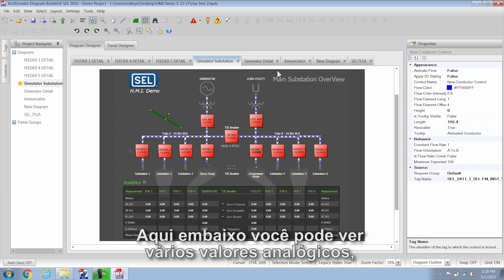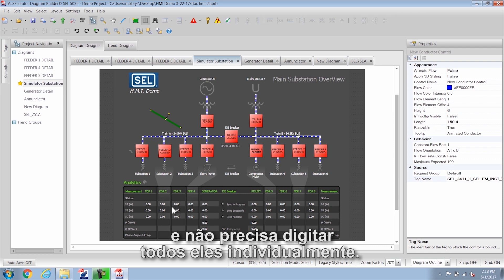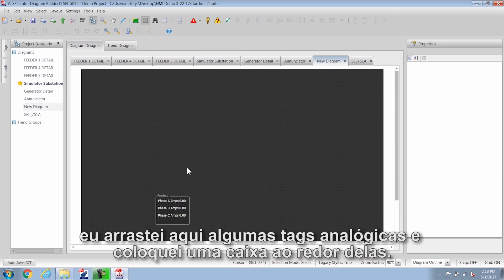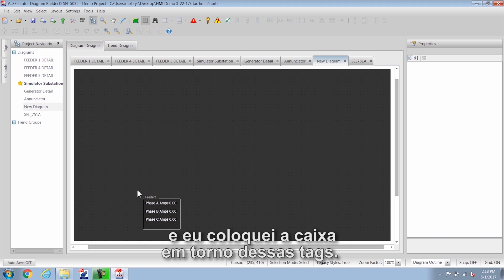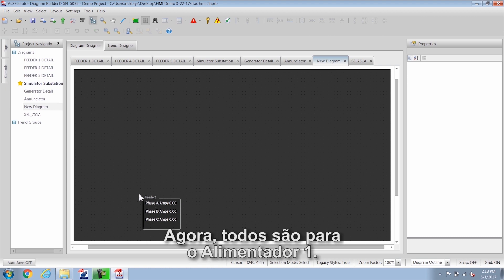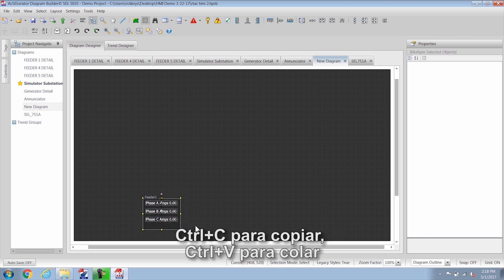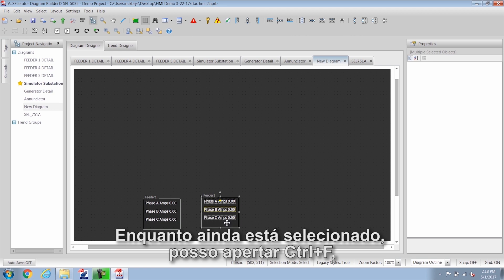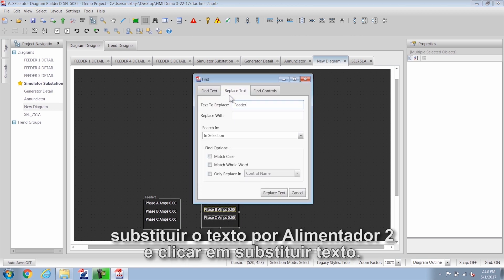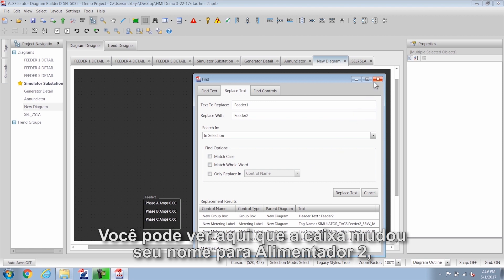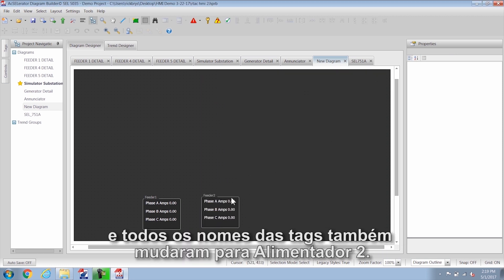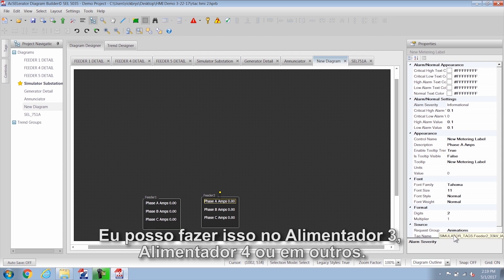Next I want to talk about group boxes. Down here you can see a bunch of analog values and you don't have to type all of them in individually. I start with a clean slate, drag over some analog tags, and put a group box around them — group boxes are found under controls. All of these are for feeder 1, so I can highlight all of it, Control+C to copy, Control+V to paste. Now I have two that are identical. While it's still highlighted I can do Control+F for find, type in 'feeder 1', and replace text with 'feeder 2'. Click replace text and you can selectively replace different things. The group box name changes to feeder 2 and all the tag names also change to feeder 2. You could do that for feeder 3, feeder 4, or whatever.